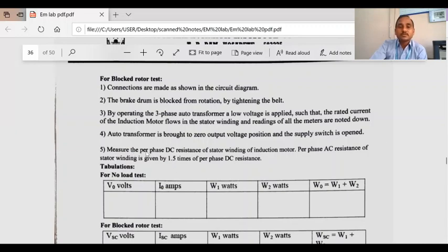And measure the per phase DC resistance of the stator winding of the induction motor. The per phase AC resistance of the stator winding is given by 1.5 times the per phase DC resistance. So the resistance can be obtained by means of a multimeter. Whatever reading is obtained for the DC resistance, multiply it by 1.5 to get the AC resistance.